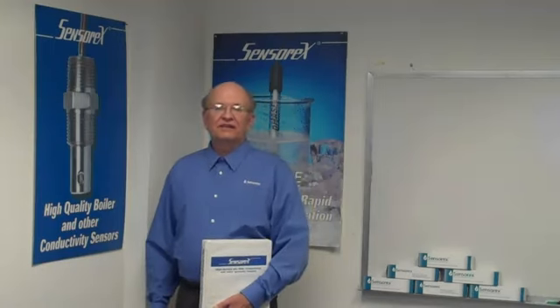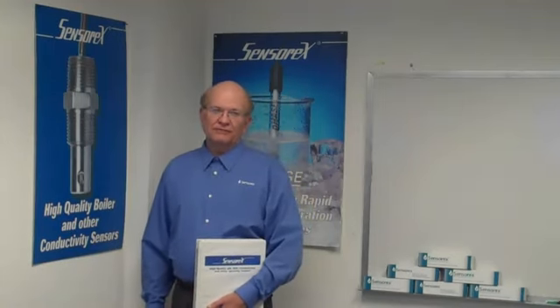I regularly get calls from customers asking how to calibrate an ORP electrode. ORP electrodes are not calibrated in buffers the way you would calibrate a pH electrode. ORP is a qualitative rather than fully quantitative measurement. This often frustrates the user who may be expecting something different. ORP electrodes can be tested to verify that they still maintain a proper output level.